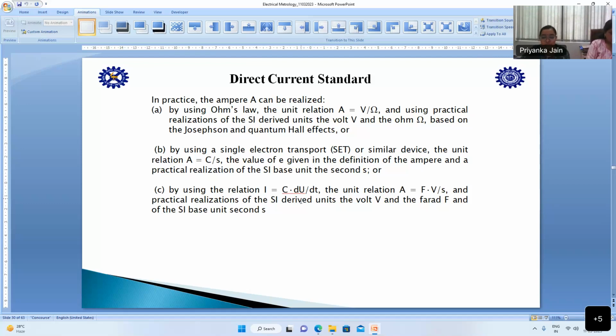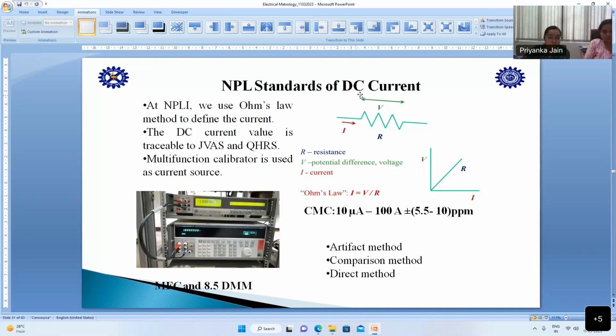In NPL, we have established a technique to generate and measure low current from 1 picoamp to 10 microamps using this capacitance charging method and Ohm's law method. Next is NPL standards of DC current. If you have seen NPL standards of QHR and JVS for voltage and resistance, here this is for DC current. We use a multifunction calibrator as source, and this is a direct source for 10 microamps to 100 amps. Using a transconductance amplifier, we are supporting up to 100 amps.